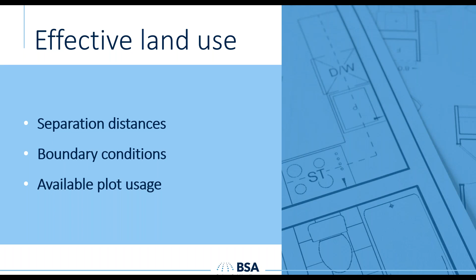One key benefit people use sprinklers for is freedom, meaning open spaces. Sprinklers are a key component of atria and the use of effective atria, used by many to increase sight lines and exit distances. Increased compartment sizes are enjoyed by both commercial and industrial properties, where sprinklers allow large compartment sizes and that open space feeling. In residential properties, people want flexibility over how they use space, and sprinklers are a component of what we now see as open plan living. People want the freedom, but they need the fire protection, and one way to give that is to balance passive and active protection by introducing sprinklers into buildings.